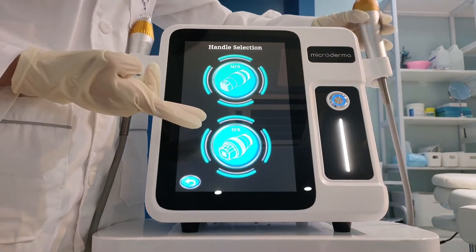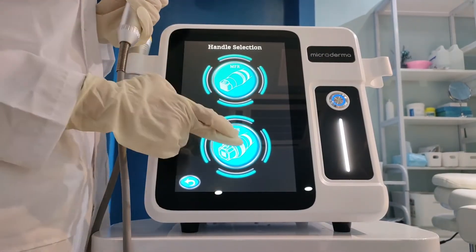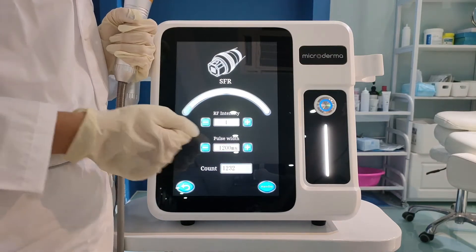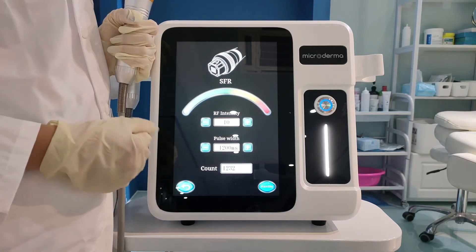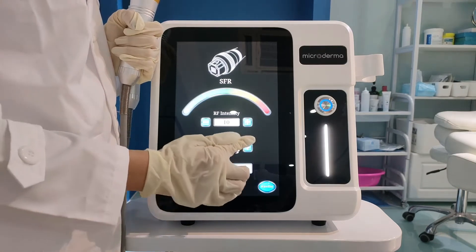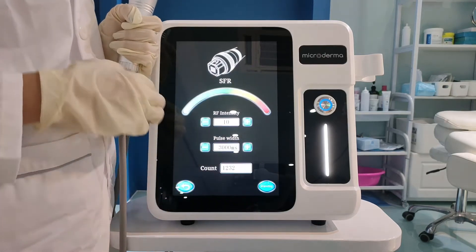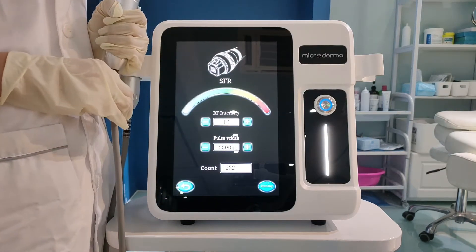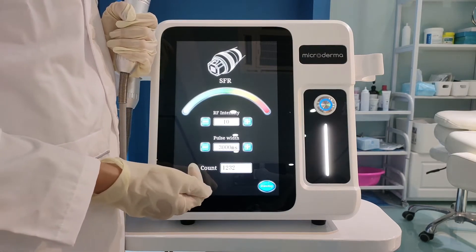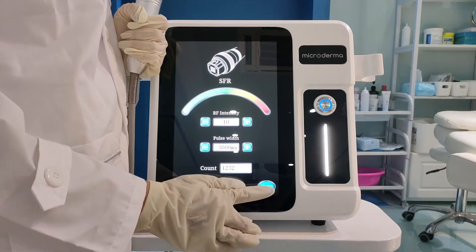This one is the non-invasive handle. This one is RF intensity; it has 1 to 10 levels. And this one is pulse width. The range is from 1,000 milliseconds to 3,000 milliseconds — it means the time the needle works in the scan. This one is count, which means how many shots the needle works. This button is standby; touch it to make the machine work.